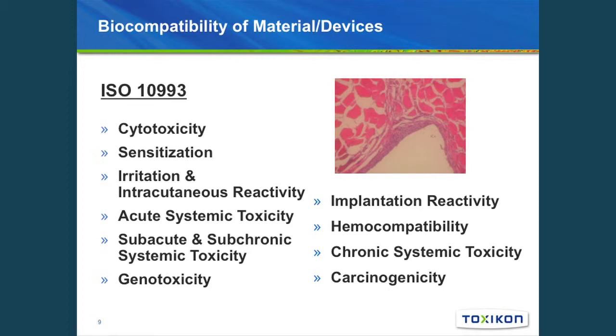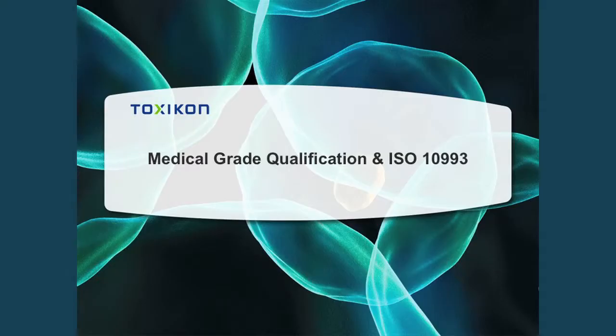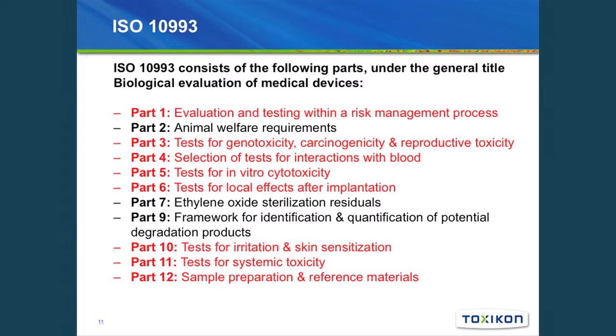Biocompatibility for medical devices follows ISO 10993, and there are a variety of assays necessary to ascertain biocompatibility of a material or medical device. It starts with cytotoxicity, an in vitro assay, and then a variety of in vivo assays like sensitization, irritation, and systemic toxicity — some of which we also saw in USP Monograph 88. The 10993 series has 20 different parts; those specific to biocompatibility range from parts 1 through 12, starting with part 1 where you define the testing requirements.